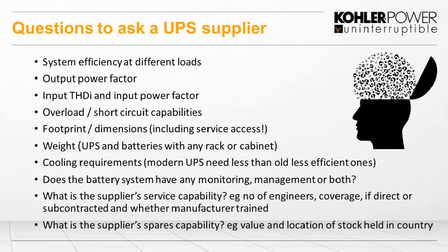So once you put that system in, and we're thinking about looking after the system, which is a good thing, do we want to have a monitoring or management system on that battery? Because this should be considered. And then the actual UPS supplier, what are their service capabilities? How many engineers? What is their coverage in the UK? Do they subcontract or use direct factory trained engineers? And where are their spares kept and held? There's no point having a 6-hour response if the spares aren't in the country to start with.